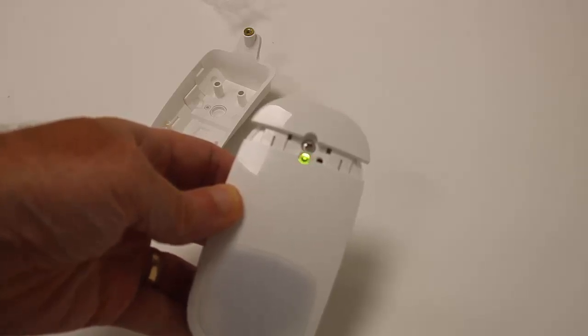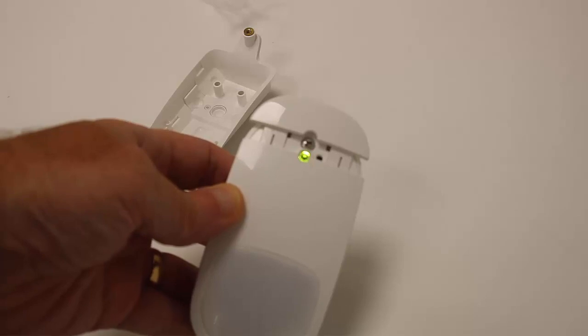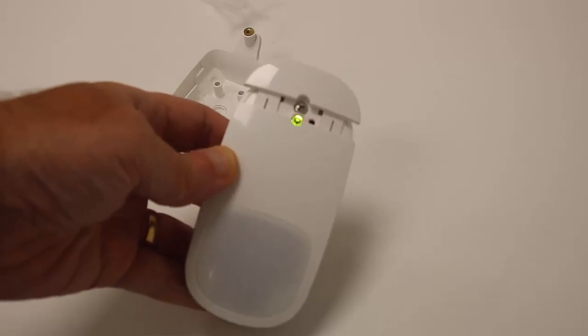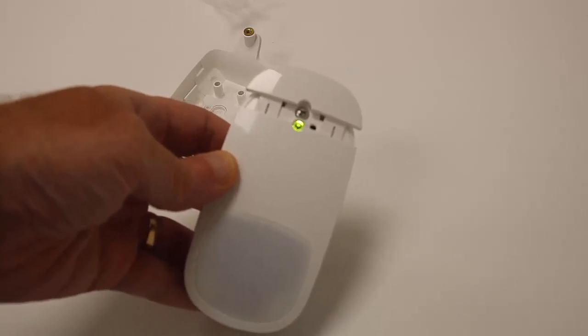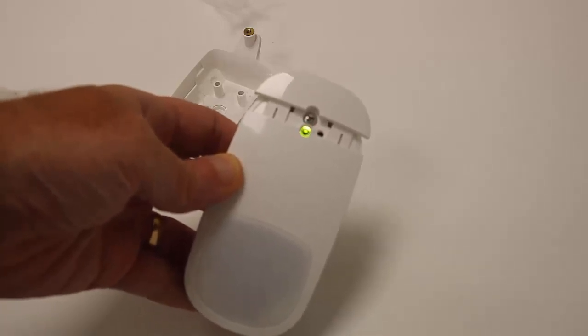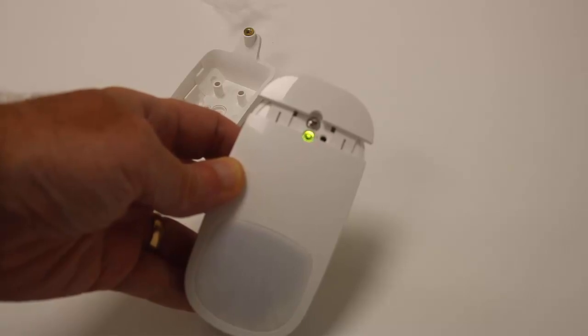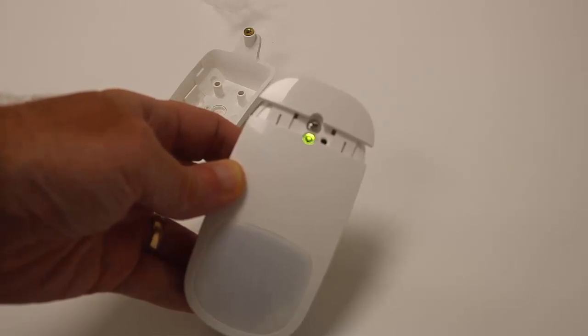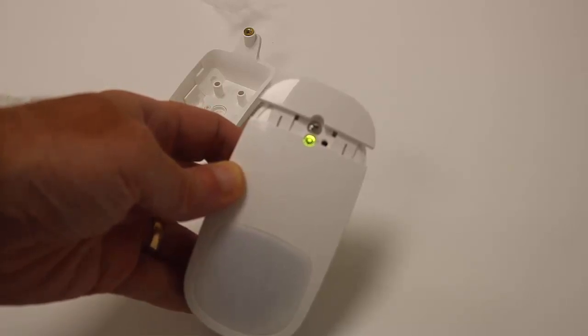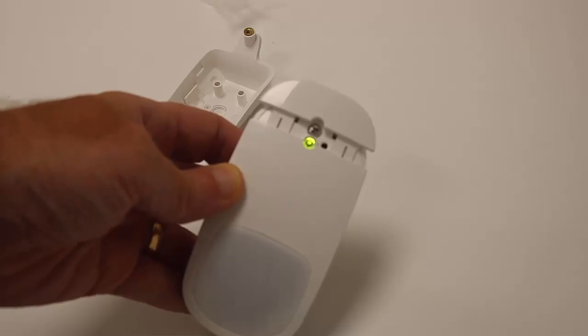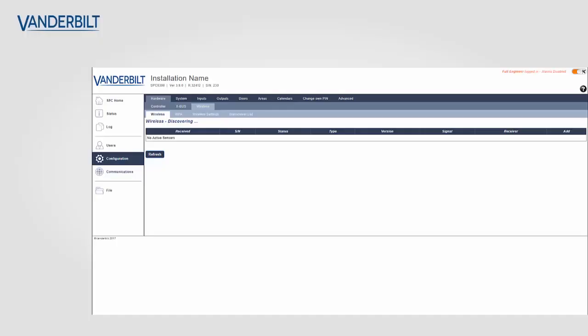At the end of this mode, it sends a 3-second enrollment transmission. This is represented by the flashing green LED. When we get a steady green LED, it means that the device has enrolled onto the SPC system.